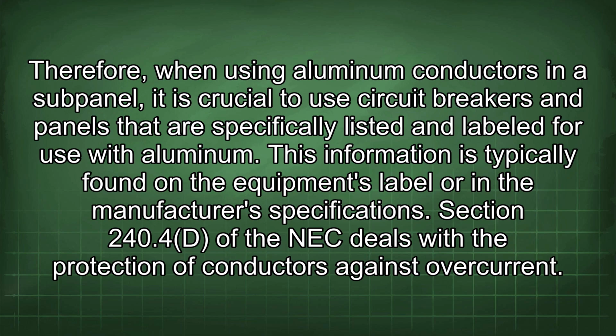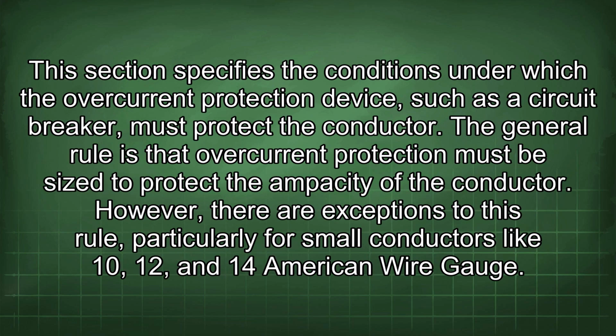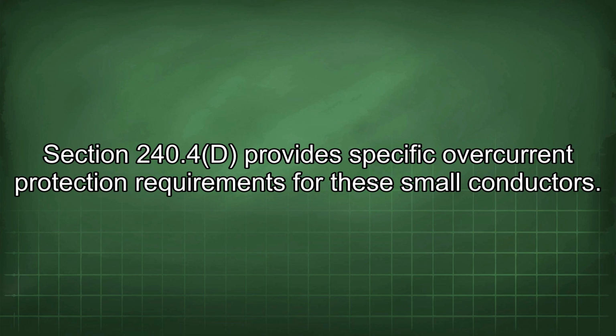Section 240.4(D) of the NEC deals with the protection of conductors against overcurrent. This section specifies the conditions under which the overcurrent protection device, such as a circuit breaker, must protect the conductor. The general rule is that overcurrent protection must be sized to protect the ampacity of the conductor. However, there are exceptions to this rule, particularly for small conductors like 10, 12, and 14 American wire gauge. Section 240.4(D) provides specific overcurrent protection requirements for these small conductors.